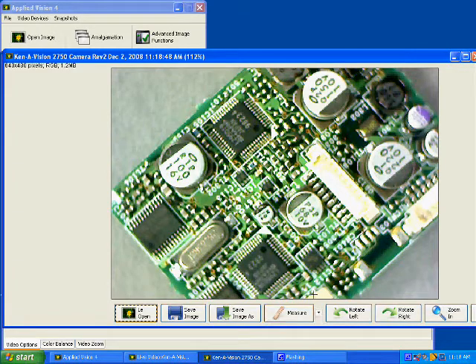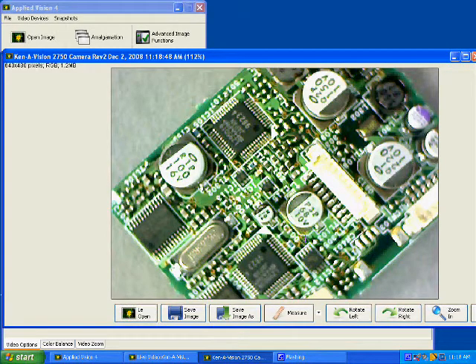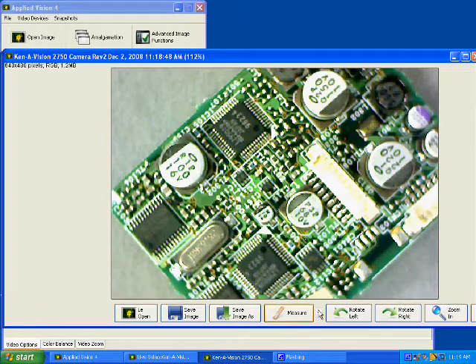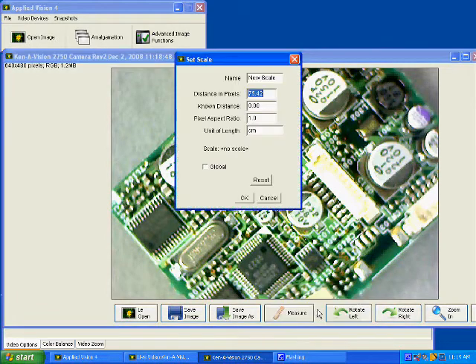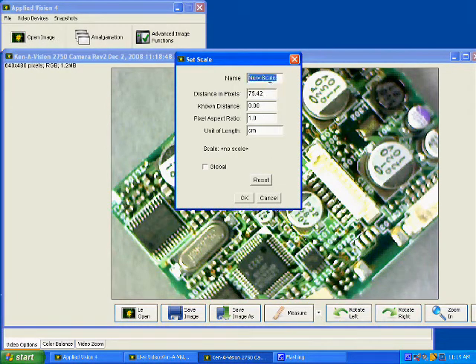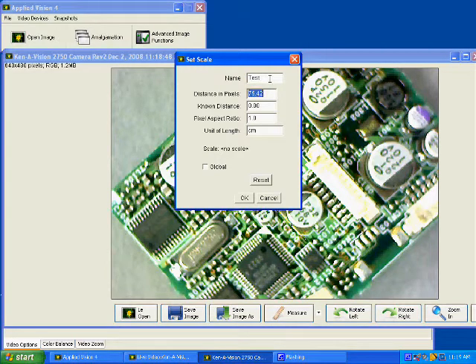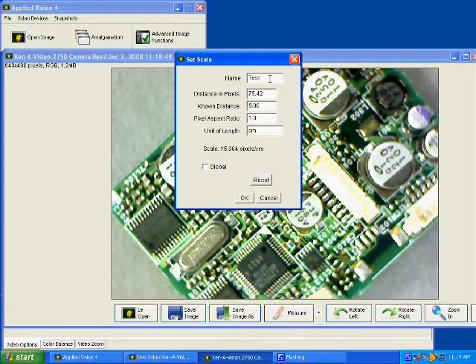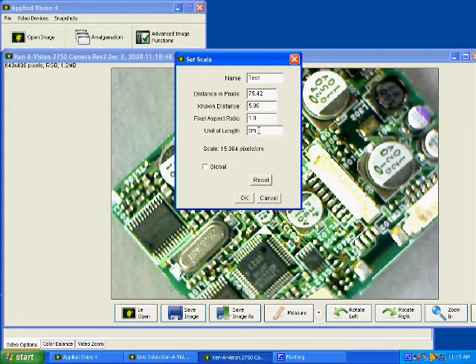Applied Vision 4 also provides a number of image measurement tools. To calibrate, a line is first drawn of a known distance. Then, the scale is set with the known distance value. After this, further lines and areas can be drawn, and measurement will capture the calibrated data.